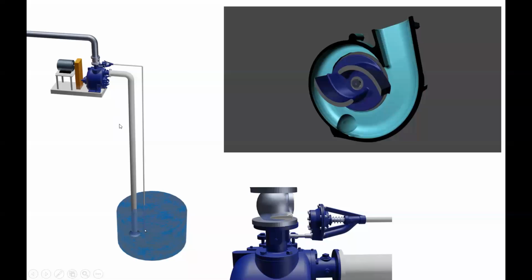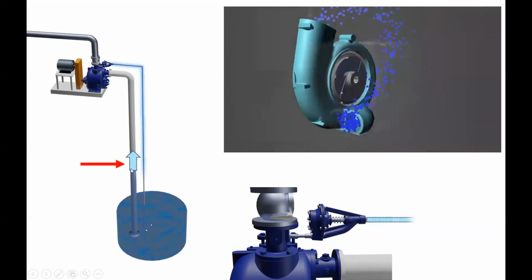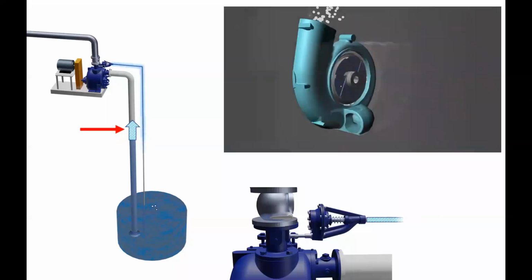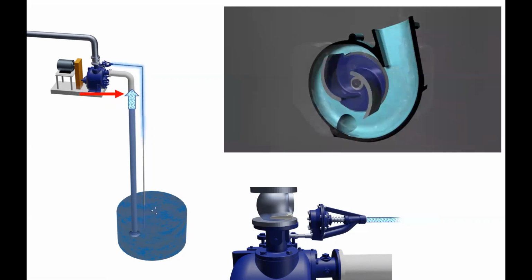And when this starts, what's going to happen is this impeller is going to throw liquid outward, creating a low pressure zone. And atmospheric pressure is going to push the fluid in this well up the straw, up the suction line. But before this liquid can get to the pump, we've got to deal with this air. So there's a story. Let's go for it. So impeller spinning. We're starting to generate a vacuum. Atmospheric pressure is starting to push this fluid up this straw, up this suction line. This air now is being pushed and mixed in the center of this impeller. Air and water is being thrown out the discharge of the volute. The water's falling back down through that recirculation port and keeping this priming going. It's refeeding the impeller, and the air is being thrown outward and rises through the air release valve and back down into the wet well. And that's the priming process.